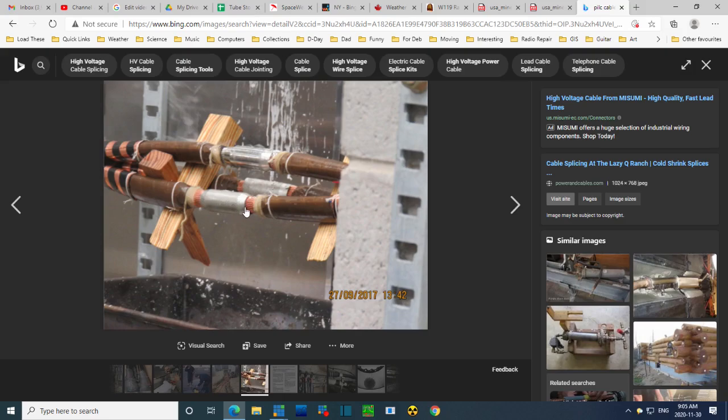There you can see the sleeves. There's no split mark. I don't think these are split sleeves. So they push the conductors all the way in until they're butted up against each other right in the middle. So they hope. It takes a lot of planning. These wires can't be moved around. Look, he's hammering wedges in here to space out the conductors. This is exactly how it's been done for like 100 years on these cables. These cables have been around for just under 100 years.